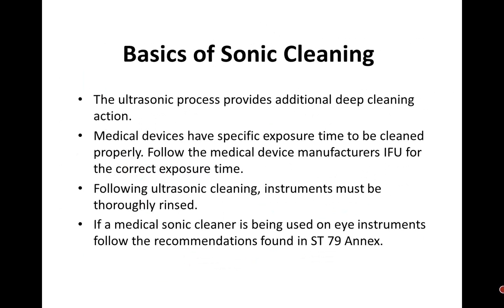And when you read the IFU, it will say rinse thoroughly. If a medical sonic cleaner is being used on eye instruments, follow the recommendations from that manufacturer, but ST79 has a specific annex that deals with eye instruments. And again, briefly on eye instruments, some you cannot use detergent or enzymatic, and some you just have to use regular distilled or deionized water. And that'll be very specific on how to use it. So again, with eye instruments, you follow the IFU from the manufacturer of those eye instruments, those surgical instruments.